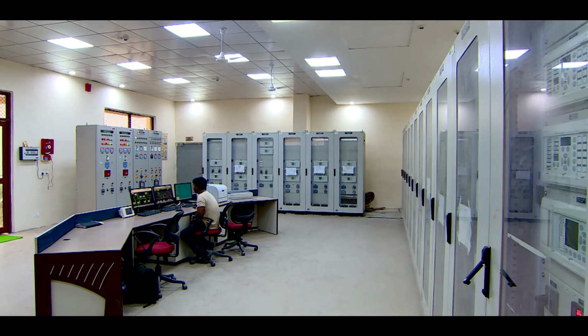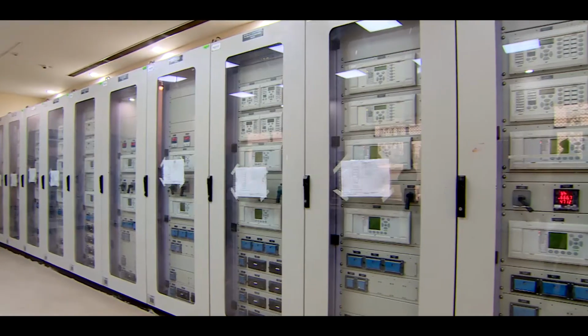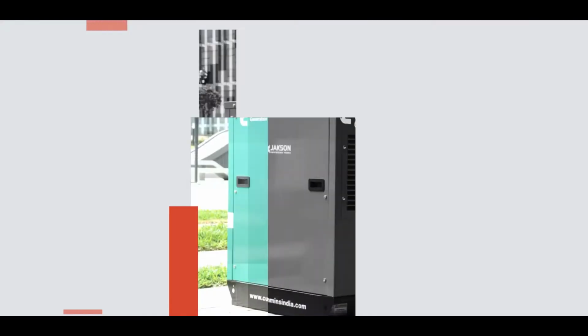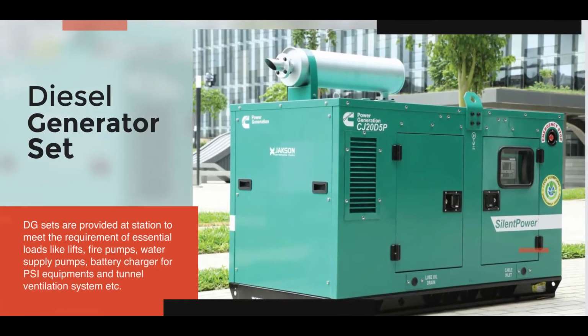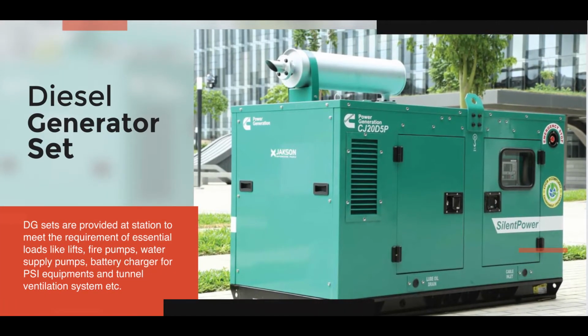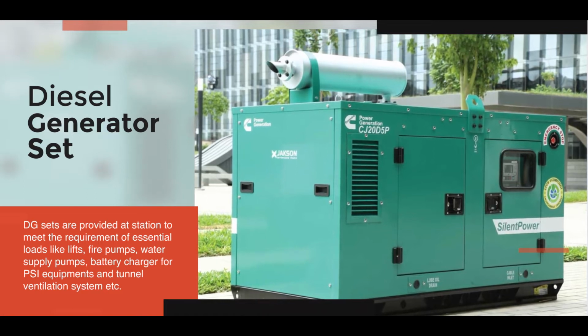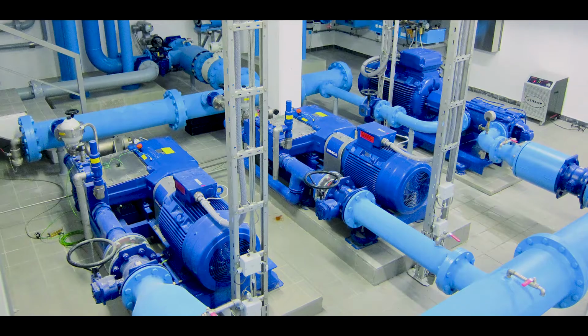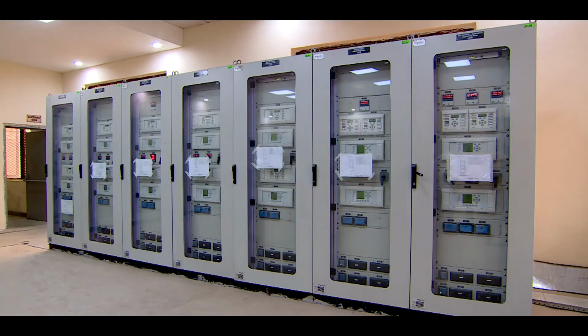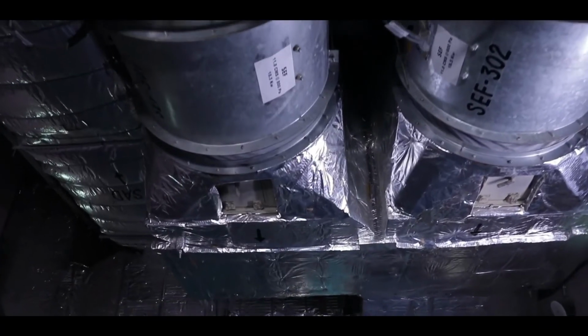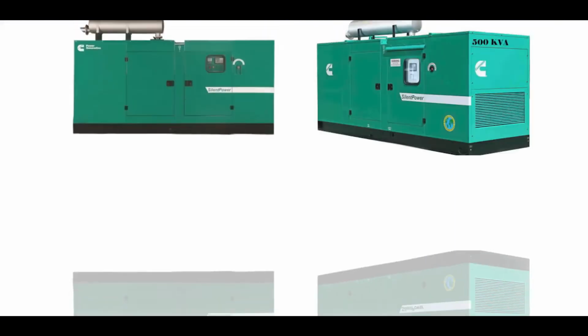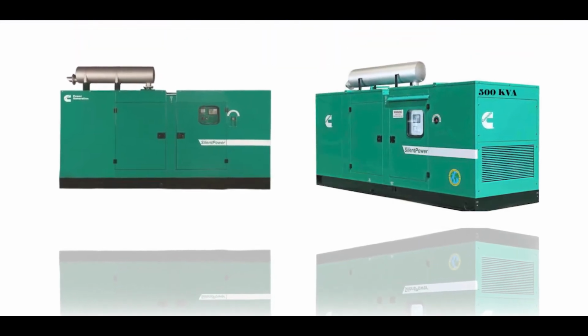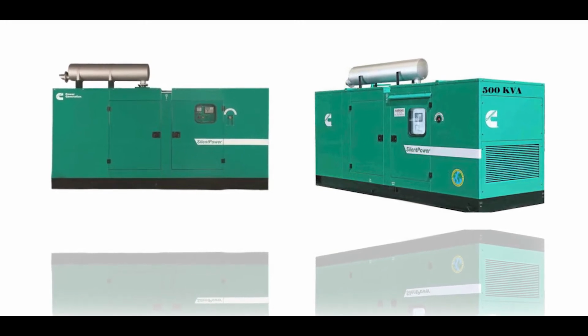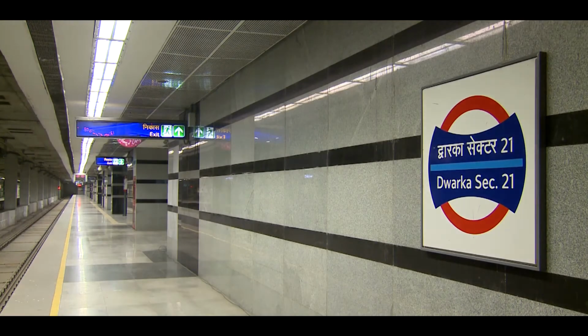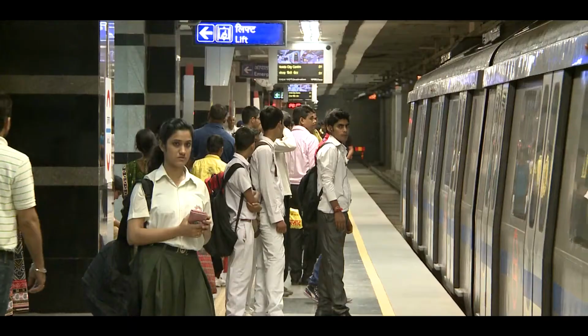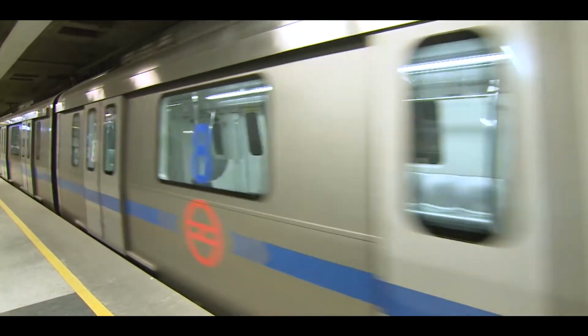Now let's briefly discuss the backup equipment used in Delhi Metro. First is the diesel generator set. Diesel generator sets are provided at stations to meet the requirement of essential loads like lifts, fire pumps, water supply pumps, battery chargers for PSI equipment, and tunnel ventilation system, etc. They are designed to operate automatically in case of failure of grid supply, so that essential power supply is available within a short span not exceeding 30 seconds.